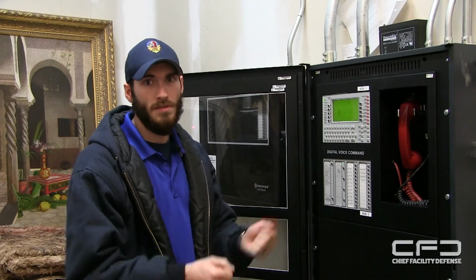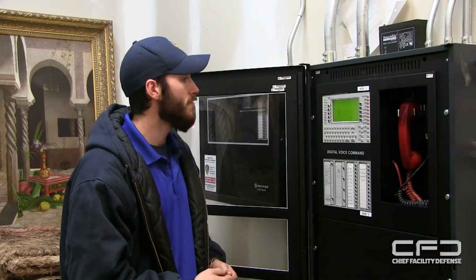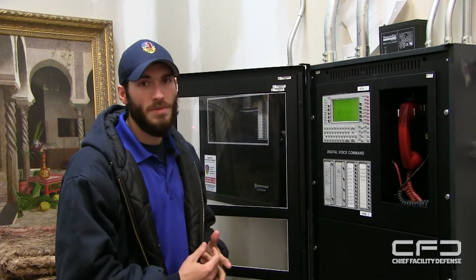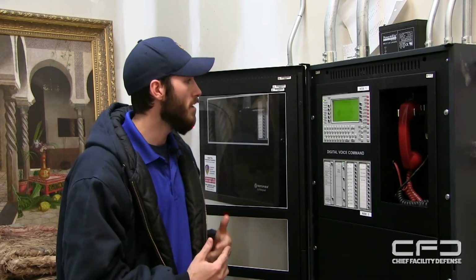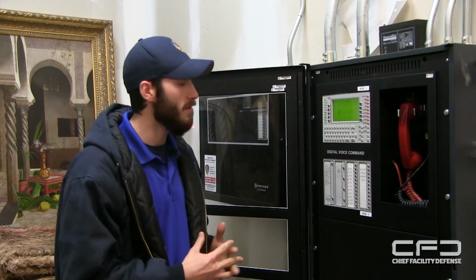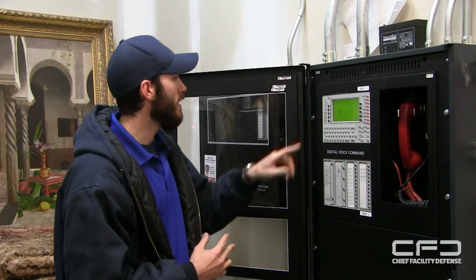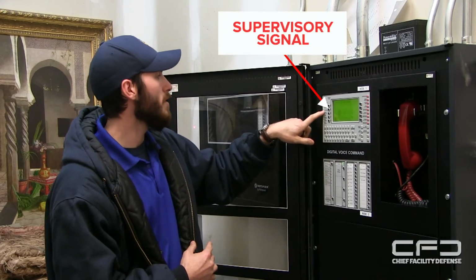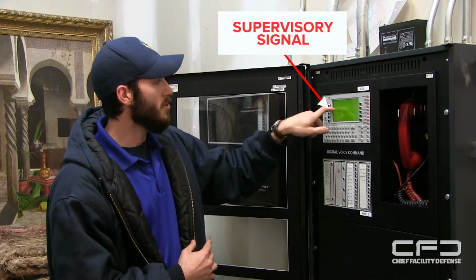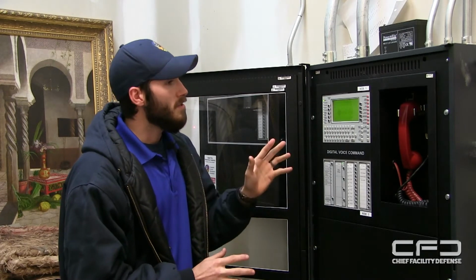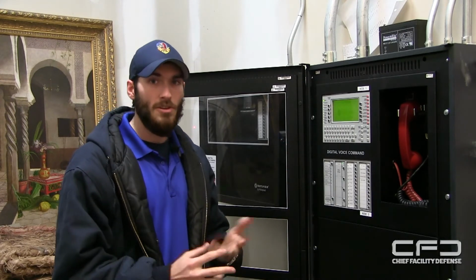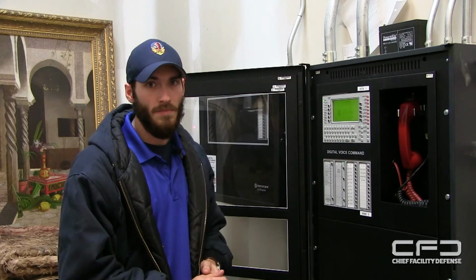On your sprinkler system, you do have tamper switch valves. You also have a few things that are part of the fire alarm system that will notify a supervisory signal. This is a signal that can come and go on occasion depending on what's going on in the building. If you do happen to have a supervisory signal, it will show you using an amber light on the left hand side, and it will also indicate on the screen what that supervisory signal is. You need to locate that supervisory to make sure that nobody is tampering with the sprinkler system or anything like that.